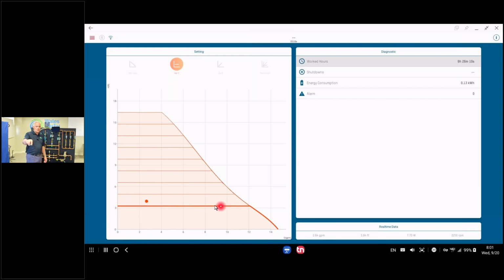Now, as I open and close the zones, you're going to see that it's going to move across this line. It's not going to move dramatically because we're not moving a lot of GPM in this system, but you'll see it change its speed. If you can see down here on your screen, I'm showing you right now the GPM that we're moving. So we are moving 2.5 GPM. I'm overcoming just under 4 feet of head, and I'm using 7.73 watts. That's all I'm using, 7.73 watts. And my ZVCs are just using a trickle of power from the capacitors that stored power earlier. So I'm not pulling any power. So my total energy consumption right here electrically is 7.73 watts.